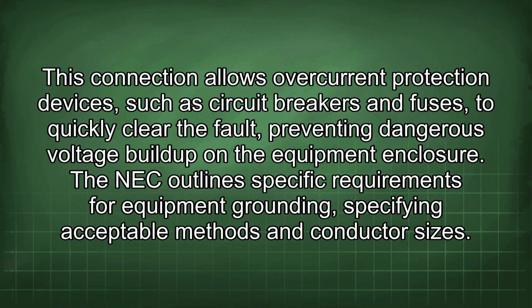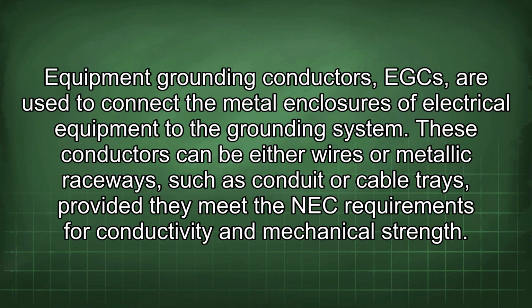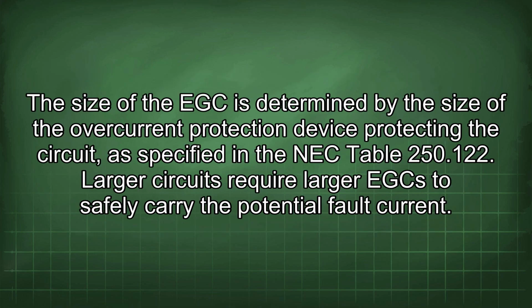The NEC outlines specific requirements for equipment grounding, specifying acceptable methods and conductor sizes. Equipment grounding conductors (EGCs) are used to connect the metal enclosures of electrical equipment to the grounding system. These conductors can be either wires or metallic raceways, such as conduit or cable trays, provided they meet the NEC requirements for conductivity and mechanical strength. The size of the EGC is determined by the size of the overcurrent protection device protecting the circuit, as specified in NEC Table 250.122. Larger circuits require larger EGCs to safely carry the potential fault current.